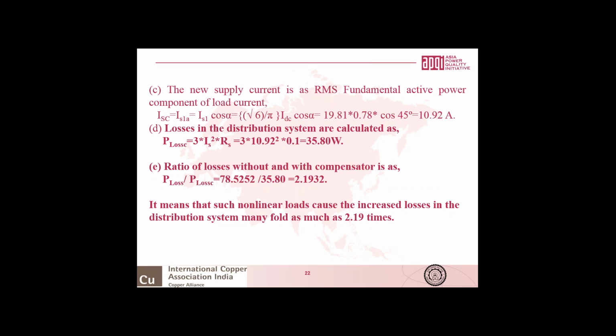So it means that such a non-linear load causes the losses in the distribution system to increase many-fold, as much as 2.19 times the losses under the ideal sinusoidal balanced current, like with unity power factor.